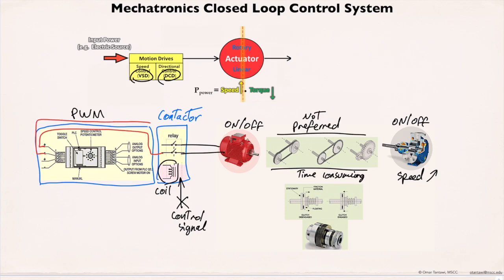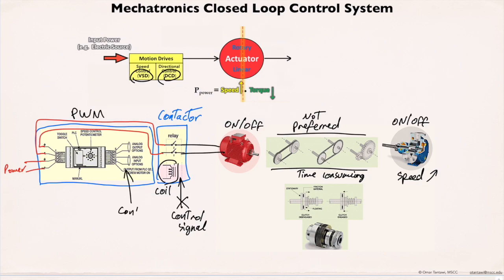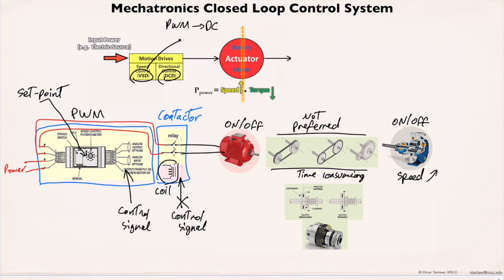A variable speed drive changes the amount of energy only when it receives a control signal, like a speed request signal, from the system controller. Otherwise, the speed is maintained at a certain set point. There are two types of variable speed drives commonly used in industry: a pulse width modulation PWM to control a DC motor, and a variable frequency drive VFD to control an AC motor.